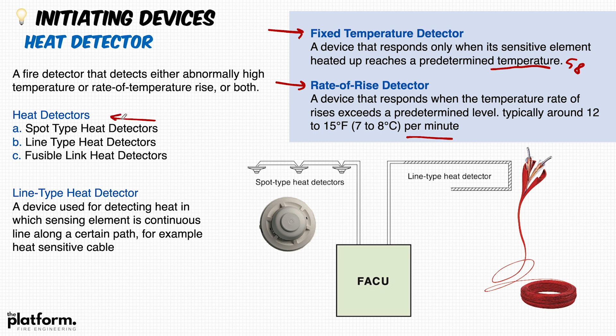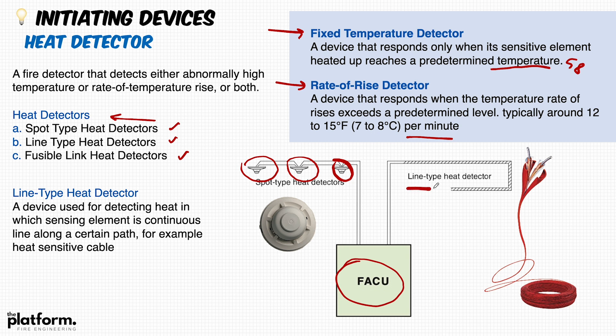Heat detectors are available in a spot type, a linear or line type heat detector, or a fusible link heat detector. Whenever you have a fire alarm control panel, spot types cover most areas as standard devices, and in some applications you can also connect line type heat detectors to the same panel using certain settings. The line type heat detector is a device used for detecting heat in which the sensing element is a continuous line along a certain path — for example, a heat-sensitive cable.